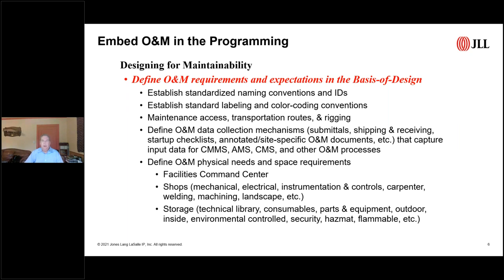Color coding is extremely helpful, especially when you have duplicate rooms with redundant equipment, to make sure people understand they're on the A side or the B side, etc. It's surprising how often somebody gets mixed up and opens the wrong breaker thinking he's on plant A when he was actually in plant B, causing an unnecessary outage.